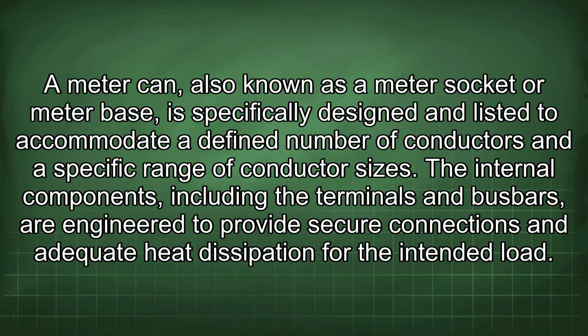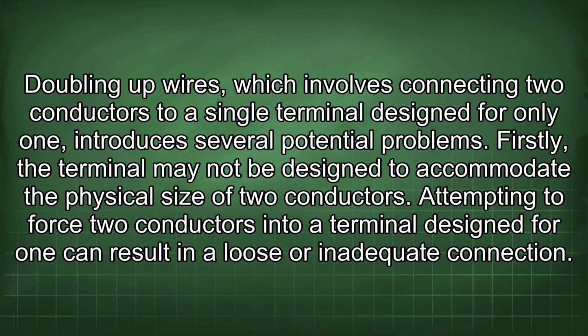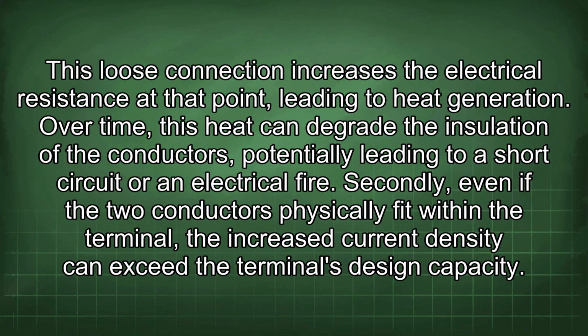The internal components, including the terminals and busbars, are engineered to provide secure connections and adequate heat dissipation for the intended load. Doubling up wires, which involves connecting two conductors to a single terminal designed for only one, introduces several potential problems. Firstly, the terminal may not be designed to accommodate the physical size of two conductors. Attempting to force two conductors into a terminal designed for one can result in a loose or inadequate connection. This loose connection increases the electrical resistance at that point, leading to heat generation.